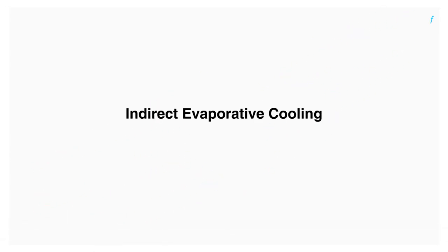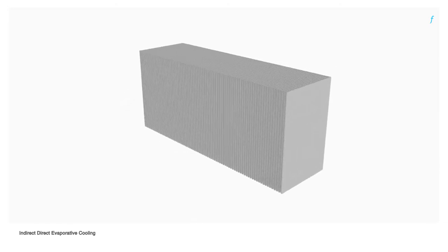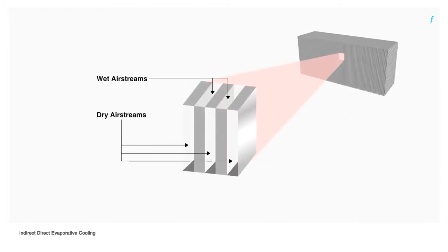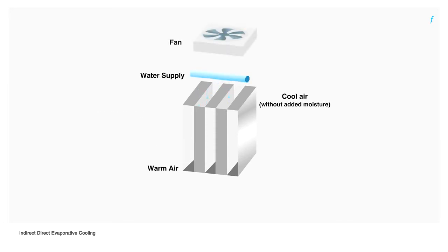The second type is indirect evaporative cooling. Here, we use a sensible heat exchanger as the medium. It consists of alternate panels, allowing wet air streams and dry air streams. Water is allowed to drip on the heat exchanger into the panels allocated for wet air streams. The fans are switched on and as warm air passes over the wet surface of the heat exchanger, water on it evaporates and the material of the heat exchanger is cooled.